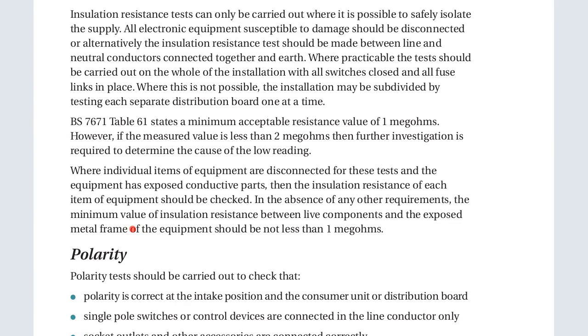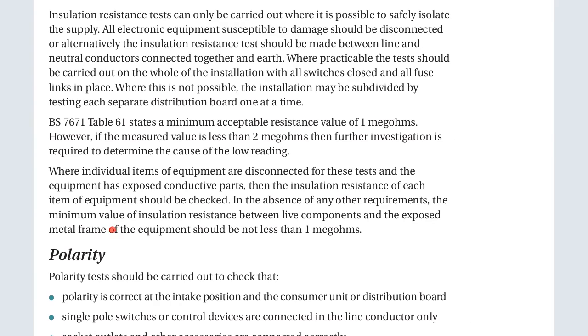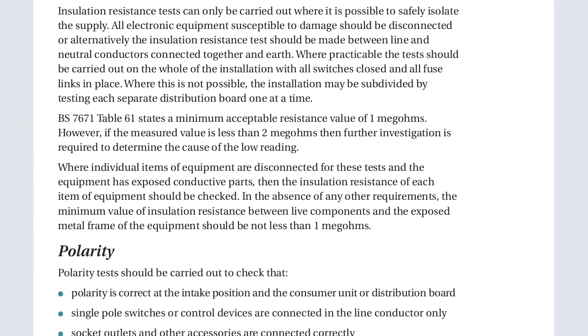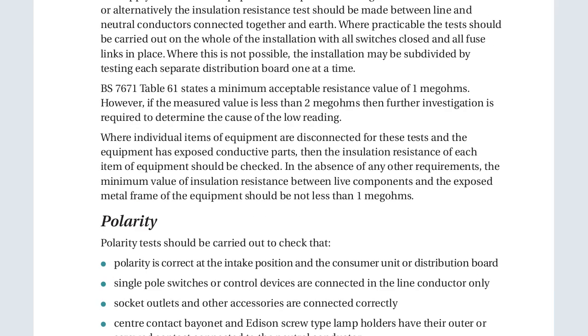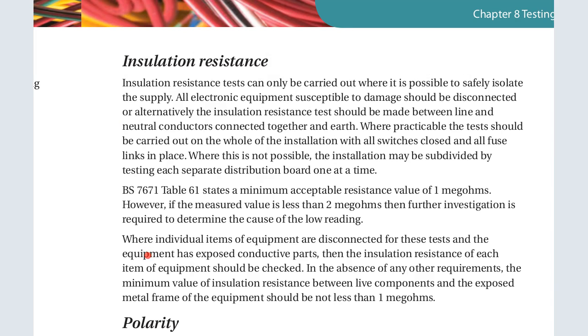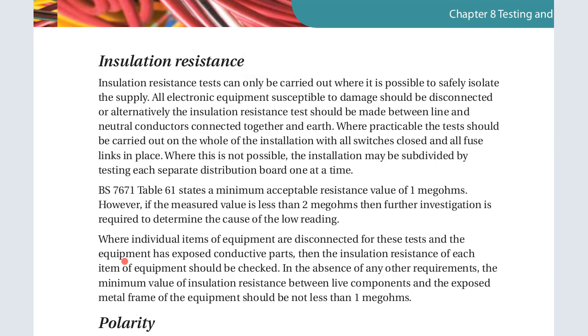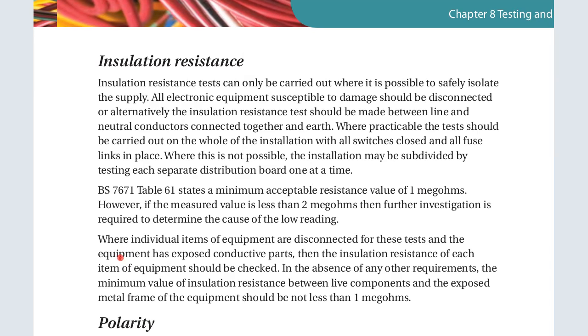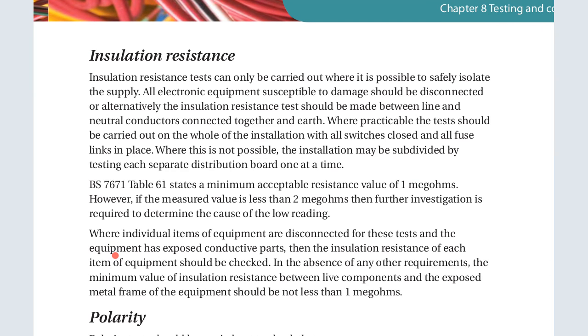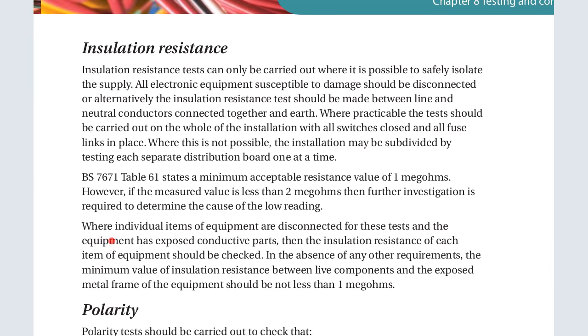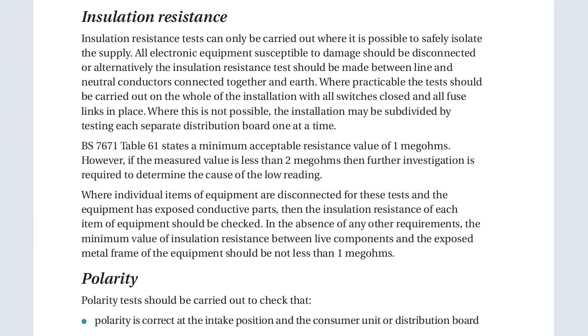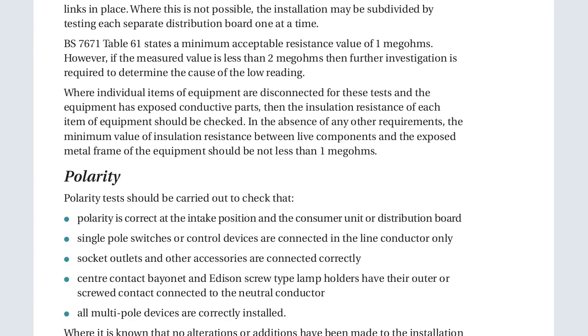BS 7671 Table 61 states a minimum acceptable resistance value of 1 megohm. However, if the measured value is less than 2 megohm, then further investigation is required. So that is the insulation resistance. We have to make sure of the safety of isolation, and that all electronic equipment susceptible to damage is disconnected. So during insulation resistance tests, we make sure that all the equipment is disconnected.